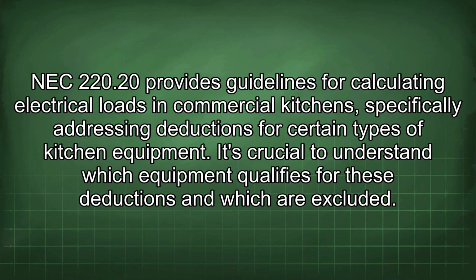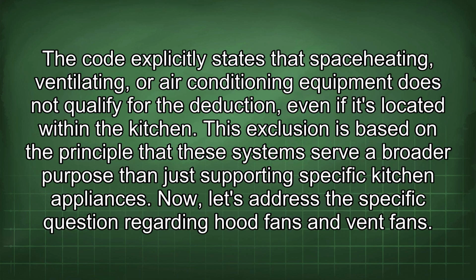NEC 220.20 provides guidelines for calculating electrical loads in commercial kitchens, specifically addressing deductions for certain types of kitchen equipment. It's crucial to understand which equipment qualifies for these deductions and which are excluded. The code explicitly states that space heating, ventilating, or air conditioning equipment does not qualify for the deduction, even if it's located within the kitchen. This exclusion is based on the principle that these systems serve a broader purpose than just supporting specific kitchen appliances.